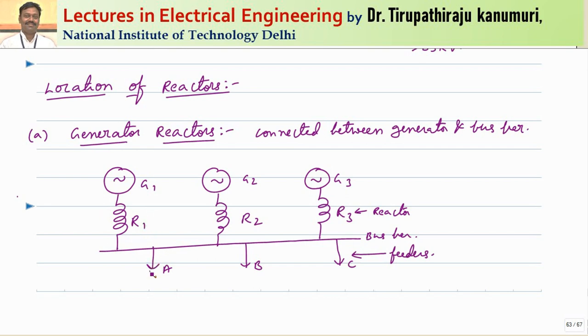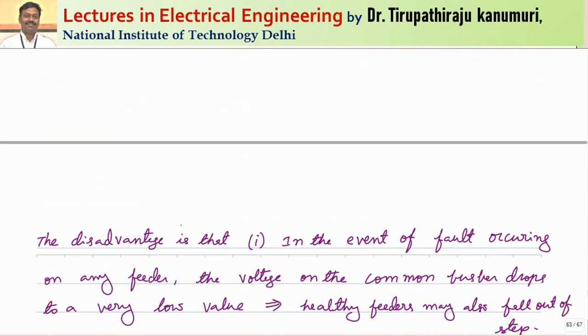The continuous voltage drop and power loss under normal conditions is one disadvantage. Under fault conditions, if a fault happens in one feeder, high fault current passes through the reactor, causing a very high voltage drop. Out of the generated voltage, the voltage appearing at the bus bar drops drastically. When bus bar voltage drops drastically, all healthy feeders are also affected because their voltage decreases too, potentially leading to system instability. Even though the fault is located on only one feeder, all other feeder voltages also decrease, causing them to become unstable or disconnect.